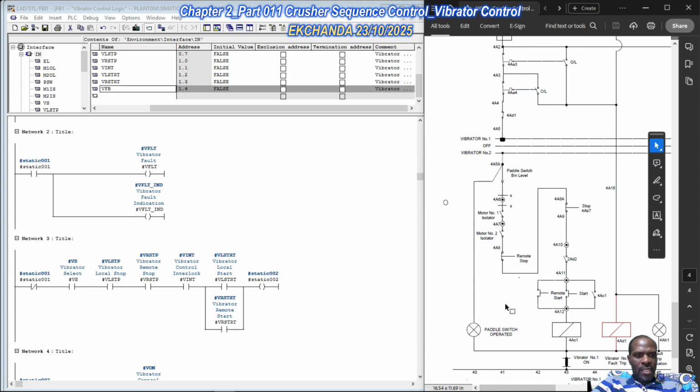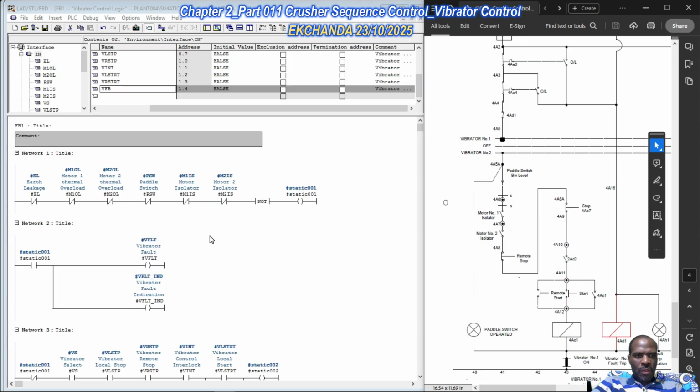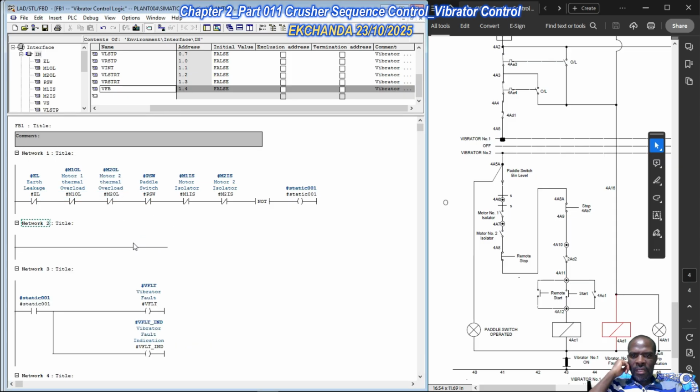Except the only thing we haven't done is the paddle switch. For the paddle switch, operated, the paddle switch is wired. paddle switch has an indication. Insert network. Internally we're using them as normally closed, because externally to the PLC they are wired through normally closed contacts, and then after input validation they are negated.